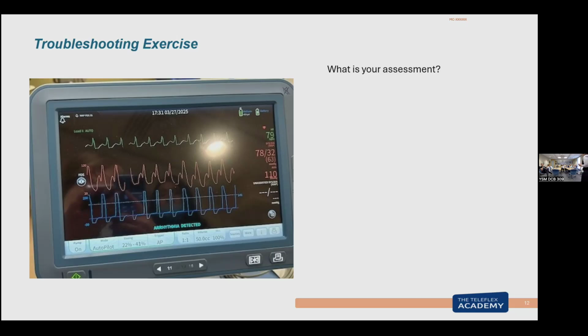The other thing that augmentation is related to is how much the balloon is occluding the aorta. So if I'm not occluding the aorta as much, volume is going past the balloon rather than being displaced, and augmentation is lower. Put the wrong size balloon in. And then position. The other thing is position. If the balloon is too low, then it's got too much distance. So that's how you get your augmentation. So when I have low augmentation on a patient and the pump's meeting all my criteria, then it's a patient-related issue that I have to look at, or position of the balloon, or is he vasodilated?